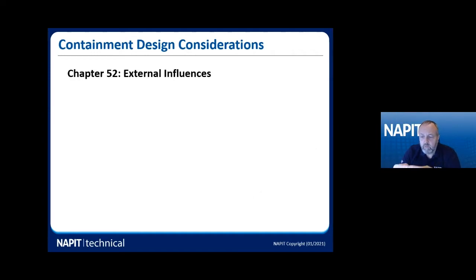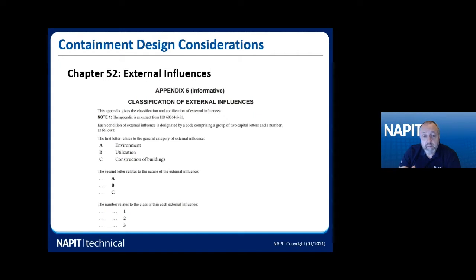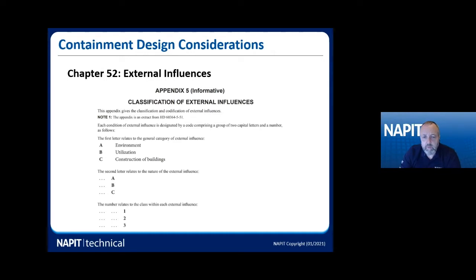We've also got to look at enclosure methods and protection against external influences. The conduit and trunking has to have a specific IP rating, or be capable of withstanding the particular external influence. When we look at external influences, we go to Appendix 5 of Chapter 52. Appendix 5 gives us all the different categories — you generally get two letters and a number, which is the IEE wiring regulations external influence categorisation. The first letter gives you the environment or utilisation, the second gives you the external influence — so 'A' is temperature, 'D' is water, and so on — and the number pertains to a particular requirement.